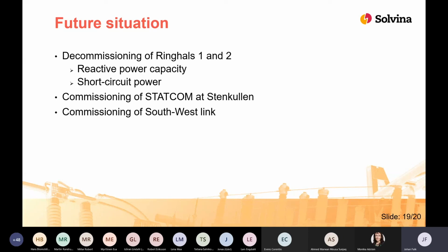The main focus of the link is perhaps active power transmission, but the stations will have a positive impact on the voltage control as well. They will add approximately 300 to 450 megavars per converter. The stations will surely be of great help in voltage control near the stations, but since the stations aren't that close to Ringhals, it's hard to predict the effect they will have in proximity to Ringhals.